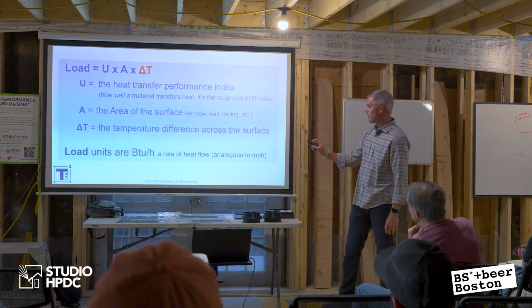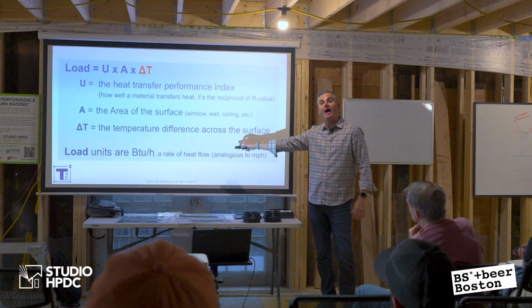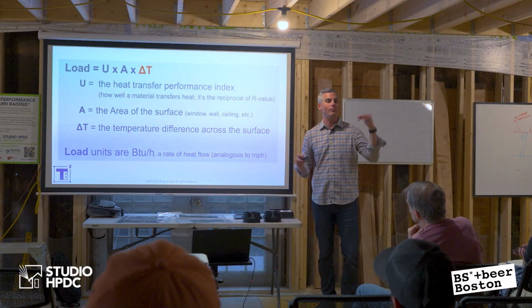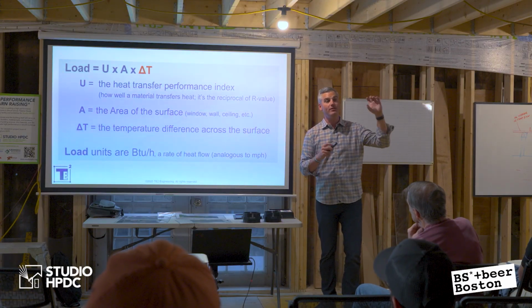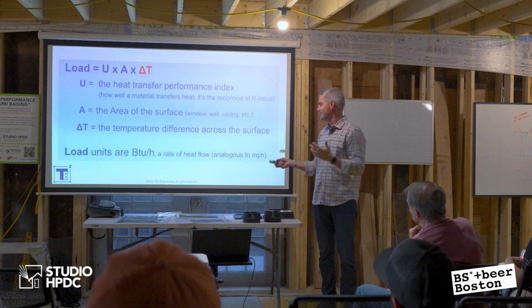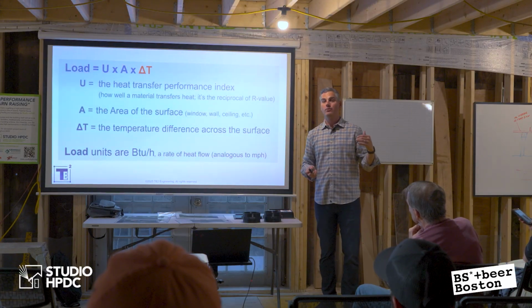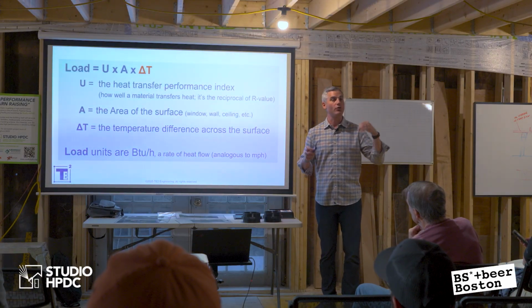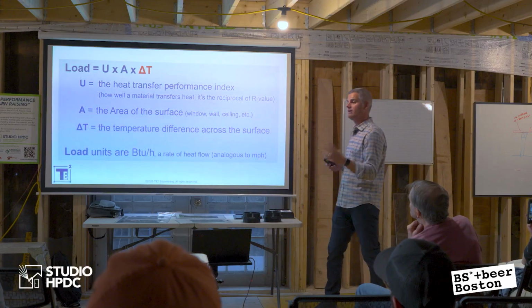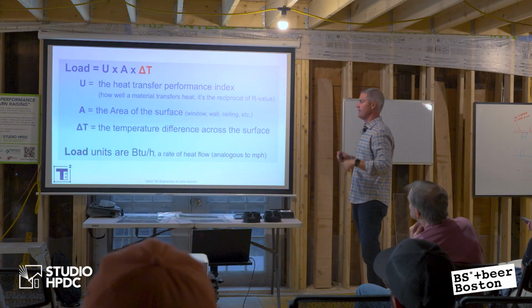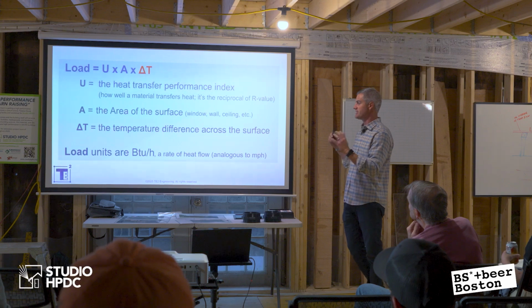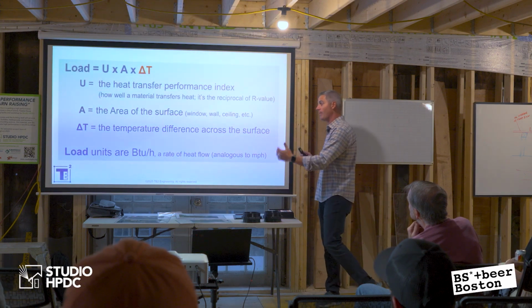One thing just to be clear on: these are BTUs per hour. People shorthand it and call it BTUs, but it's really BTUs per hour. It's analogous to miles per hour, right? It's like a velocity or a speed. It's a rate of heat transfer, BTUs per hour. I'm very much a stickler for units. BTU per hour matters, not BTUs.